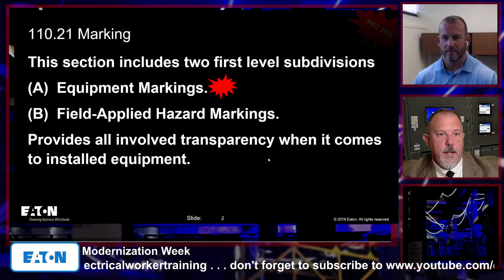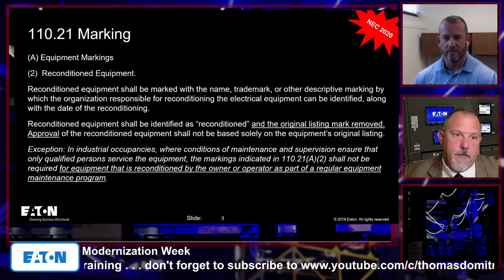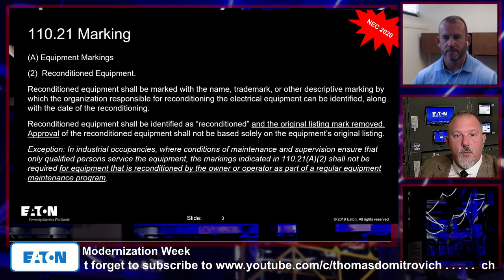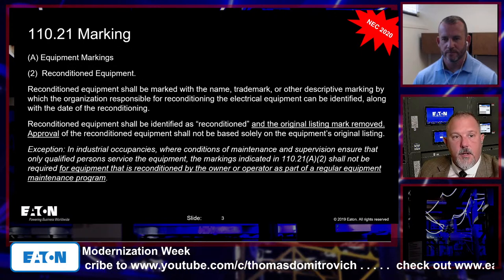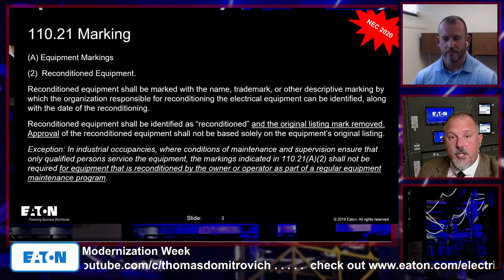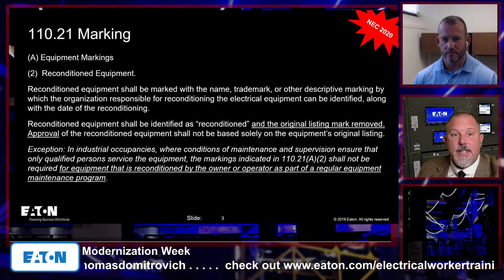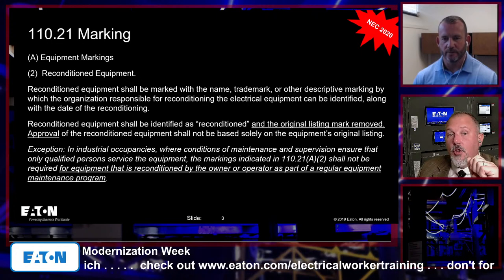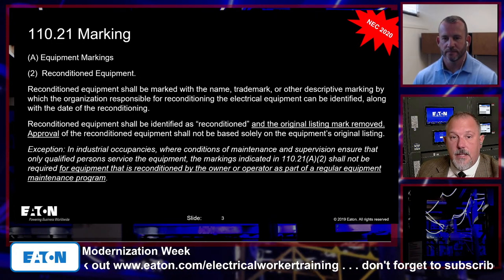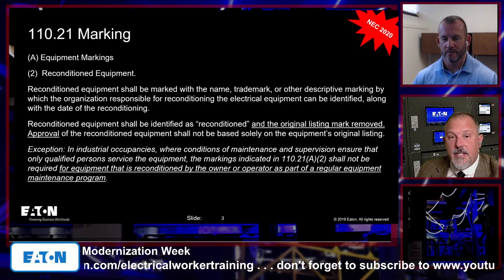Now I'm just looking for it because there is... there it is. So there's a new requirement in the 2020 code that basically tells us, you have equipment marking, you have field, and I think it's in A, A2 is reconditioned equipment. It says reconditioned equipment shall be marked with the name, trademark, or other descriptive marking by which the organization responsible for reconditioning the electrical equipment can be identified, along with the date of reconditioning. So now you also have to remove the existing listing mark, and it has to be identified as reconditioned.